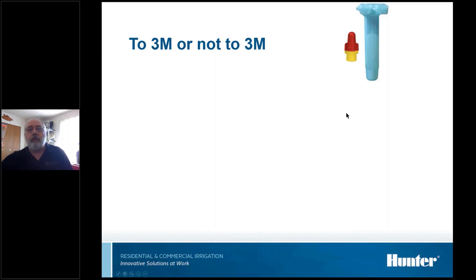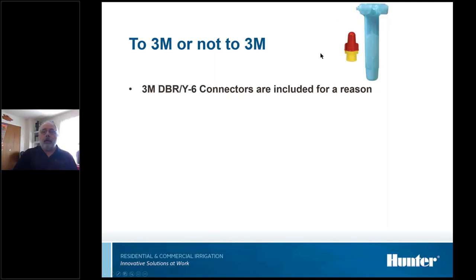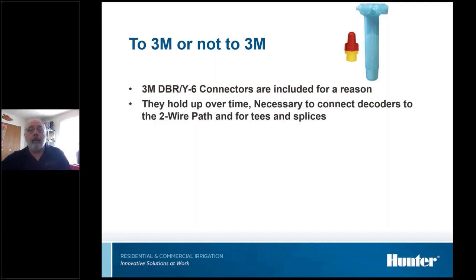The other thing we get is, do we have to use them connectors? Basically, yes, you do have to use them. We've tested all the different manufacturers' connectors, and this one, the 3M, is just hands down, in our opinion, the best one. It's got the best grease in it. It holds the wires into the wire nut better than the other ones do. It holds the wires into the grease pack better than the other ones do. It's just a better connector. It passes our tests better than any of the rest of them. There's others that meet the electrical specs. They're just, in my opinion, not as good. And the whole thing is, you can put anything in to begin with and it'll work, but over time, you'll have issues if you don't use the right connectors and put them in correctly.